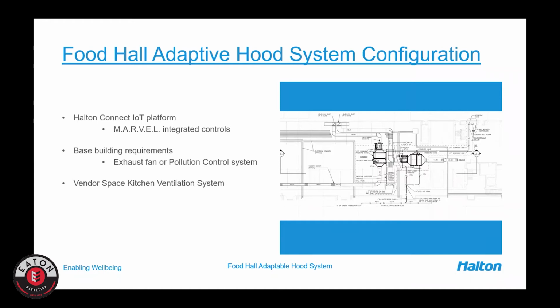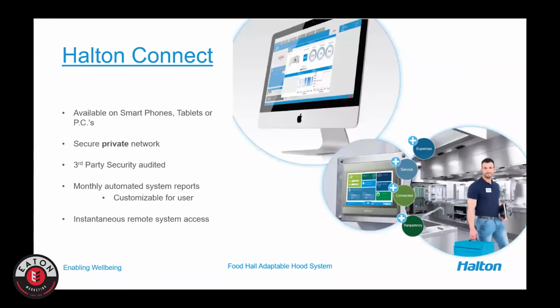The base building requirements that we need to consider early on include the overall number of vendors that will be in the space. We've worked on systems that have had 4 or 5 vendors in a given area. We're working on halls right now that have up to 50 different vendors. So these are very critical concerns when designing a system. And then the vendor components, which typically are the hood and the controls platform tied in at each individual location. Halton Connect is our monitoring system.